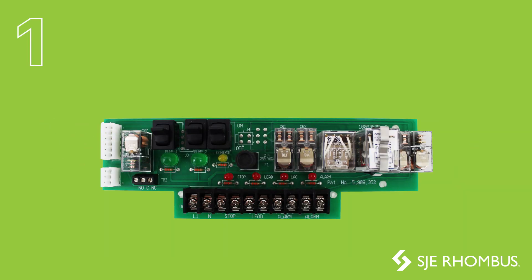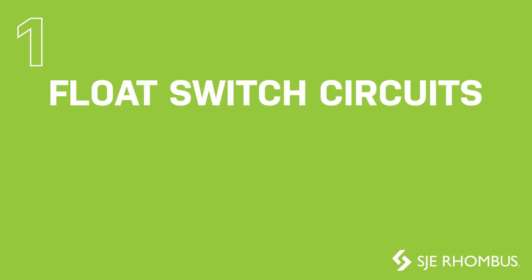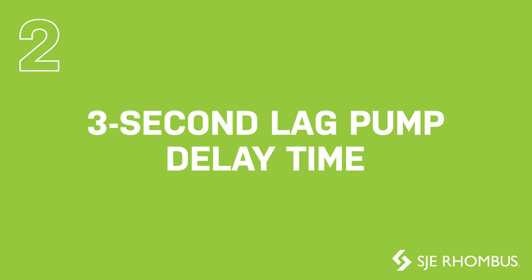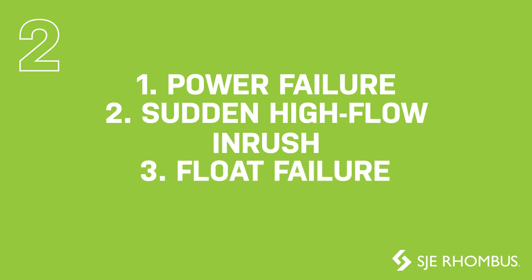The controller board has been redesigned to fit into a sleek-looking, touch-safe enclosure with detailed labels to make installation and operation more user-friendly. In addition, the float switch circuits are now low-voltage for added safety. A three-second lag pump delay time has been added to prevent simultaneous activation following a power failure, sudden high-flow inrush, or a float failure.